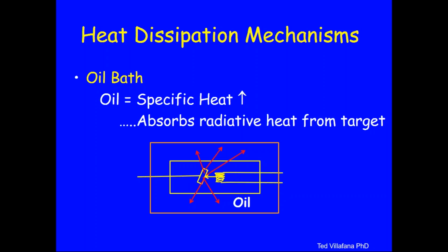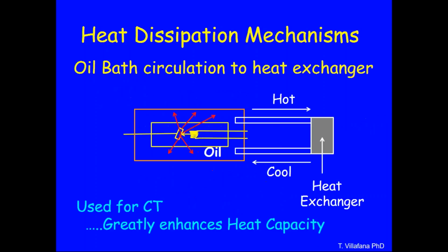So oil that completely bathes the glass envelope, over this whole region here, serves as a very efficient mechanism of removing the heat that's being radiated from the target, and a very important source of heat dissipation. And we take that one step further with CT scanners.